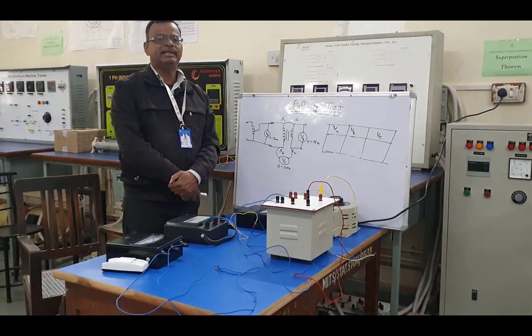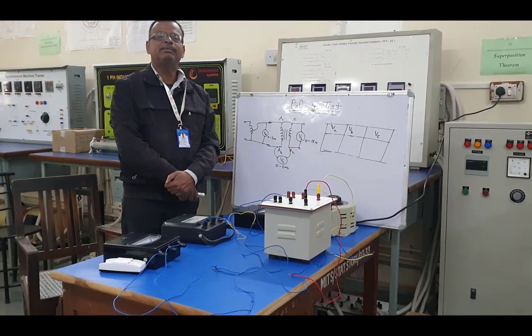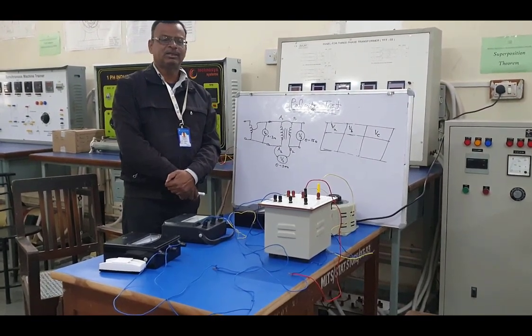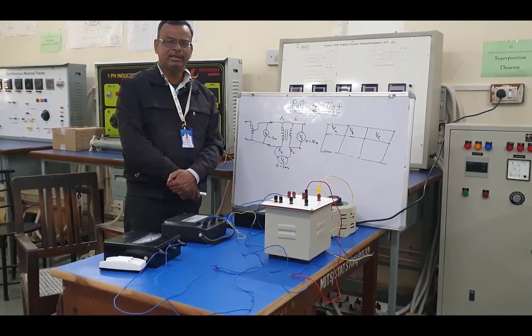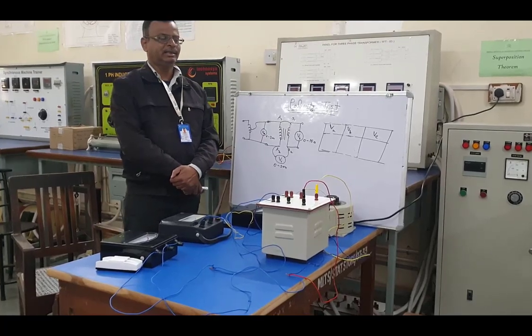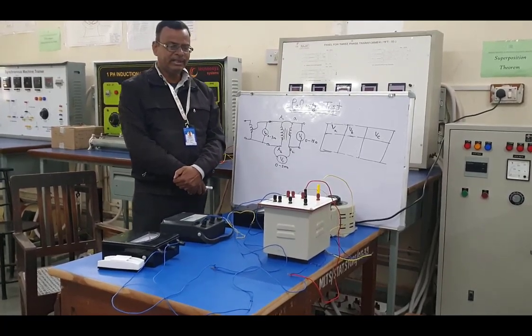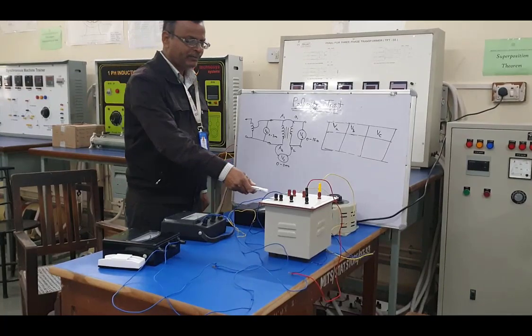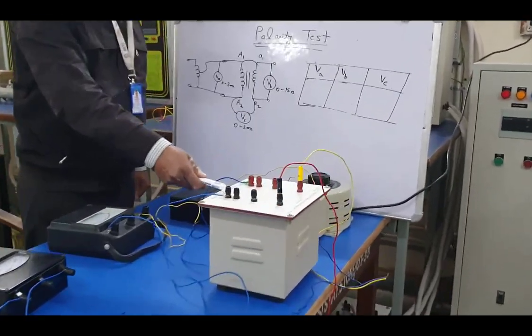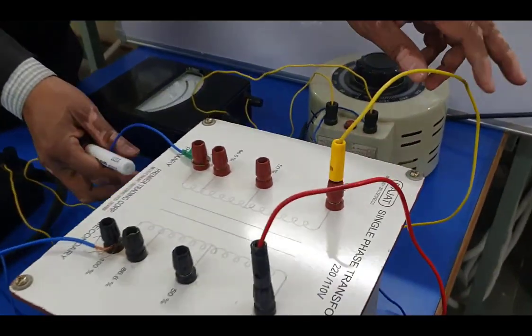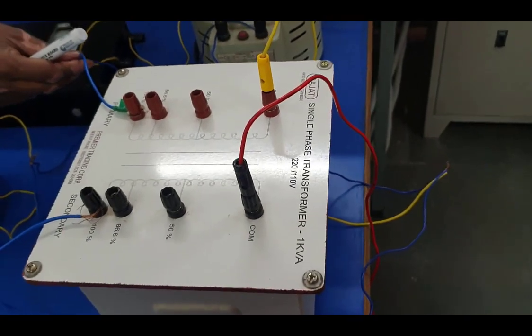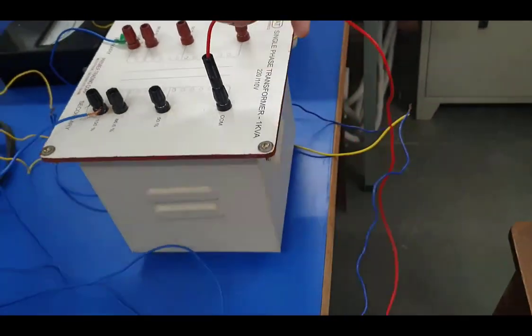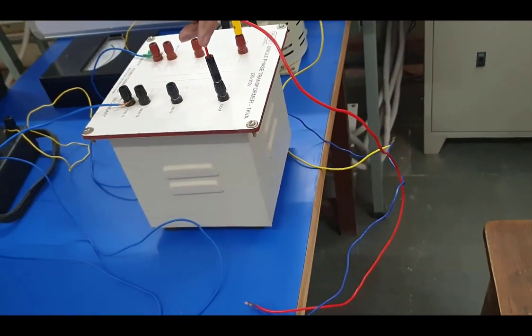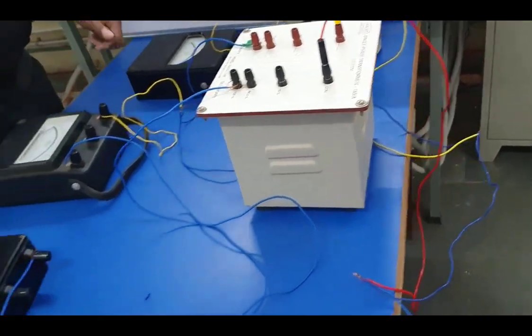Basically, the polarity test is necessary for the parallel operation of the transformer. So in this experiment we will learn how to check the polarity. For the polarity test we are using a single phase transformer. We have 220/110. 220 is the primary voltage, which is the higher side, and 110 is the secondary voltage, which is the lower side.